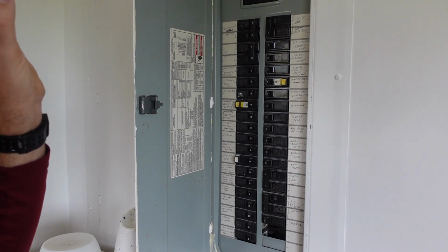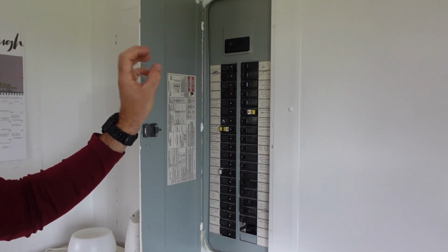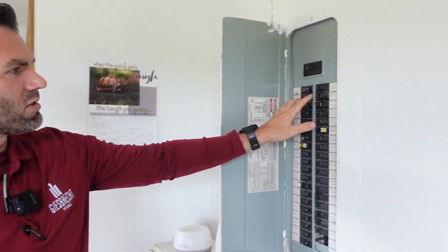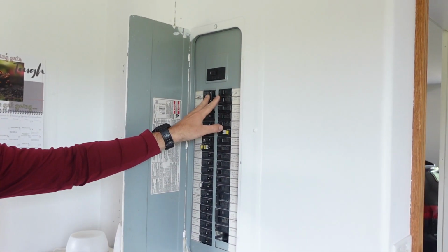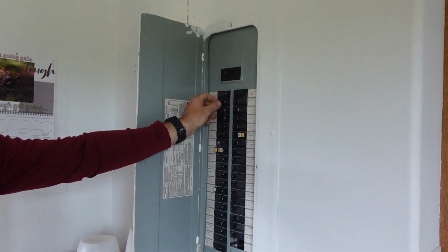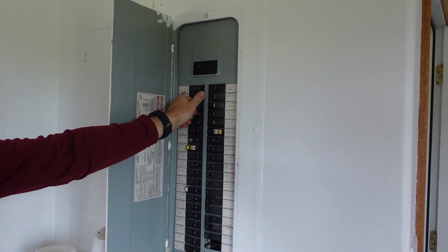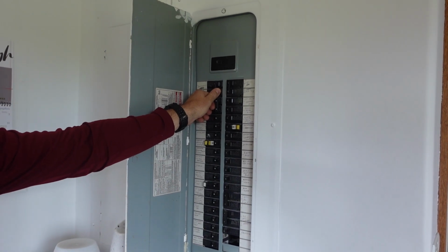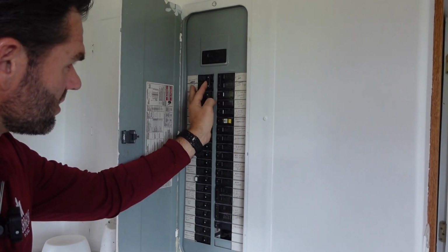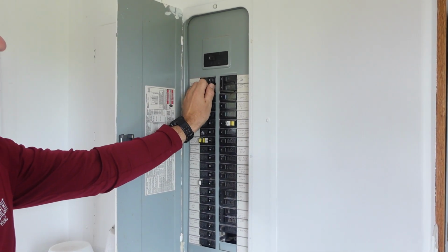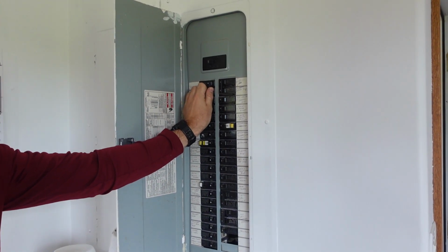Typically an air conditioner, outdoor unit or an indoor unit, is going to run something between a 20 amp to a 60 amp. Could be a little bit bigger or a little bit smaller, but not typically. And it's most always going to be a double pole breaker in our region. So if you find a breaker that's tripped, it's going to look something like this. So this is the off position. This is the on position. The trip position is going to be about right there in the middle.